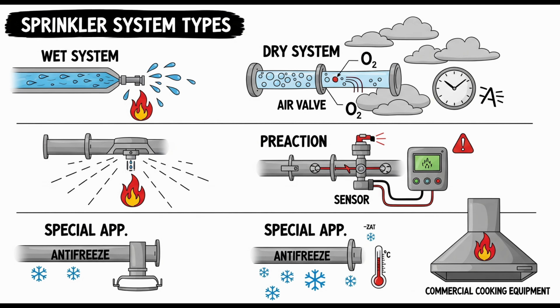Some sprays past, some might evaporate quickly in the intense heat. The standard accounts for this inefficiency in surface wetting by only using half of the sprinkler's nominal flow rate in the calculation for the required application rate on the surface itself. Interesting. So the standard adjusts the calculation based on how effectively the water from that type of sprinkler is likely to be applied to the specific surface type being protected.